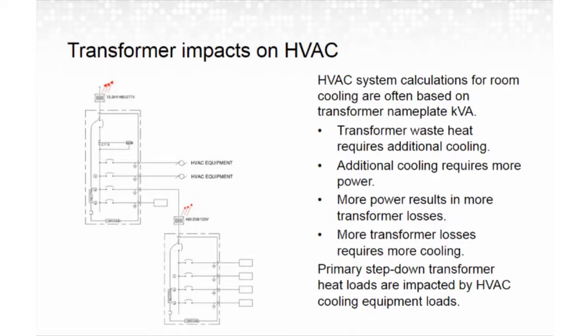The temperature rise rating for transformers in a building will affect how the HVAC system is sized. And the HVAC system is required to provide cooling for those spaces. There's sort of a cyclic nature to HVAC sizing, in that the HVAC system increases to provide cooling, and therefore so does the load on the electrical system, which can then increase the size of the transformers, which can then increase the size of the HVAC system. Locating the electrical service transformer outdoors can reduce the interior building load, which then reduces the load on the HVAC system. When the service transformers must be indoors, choosing a lower temperature rise may be prudent.